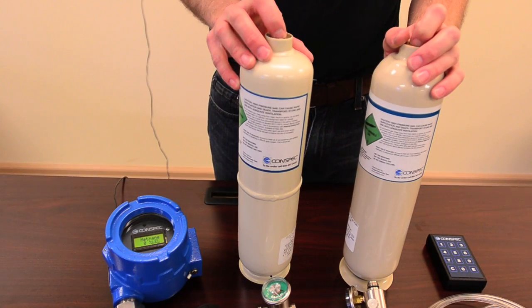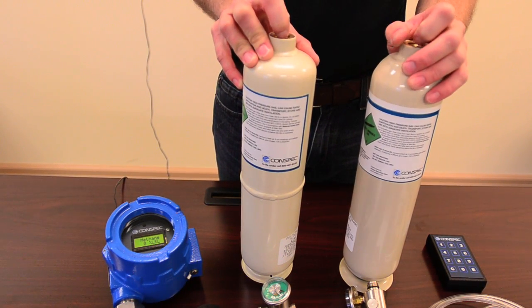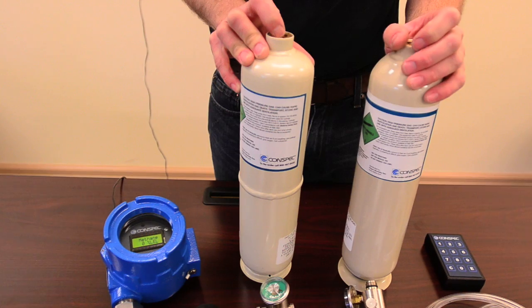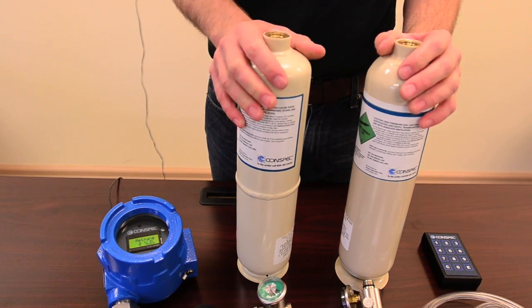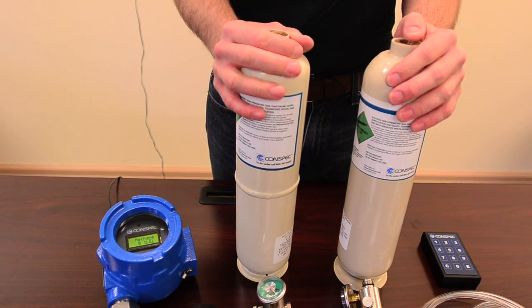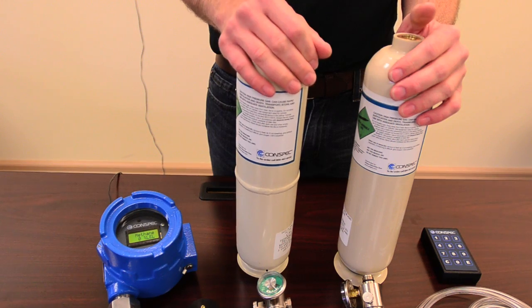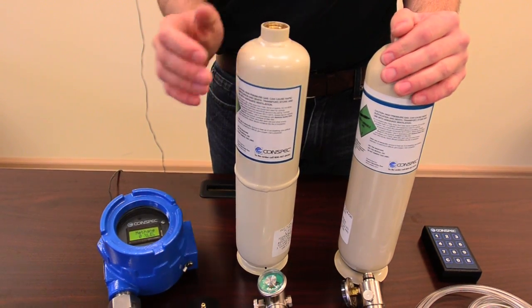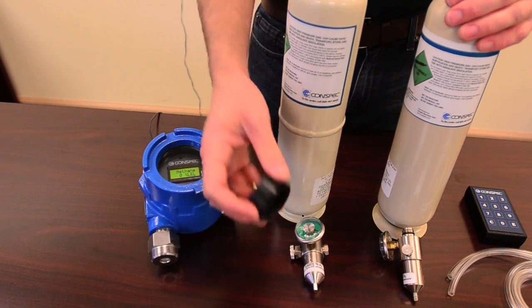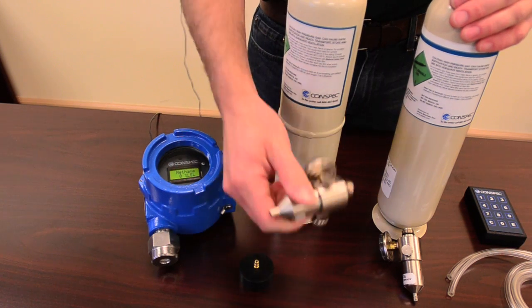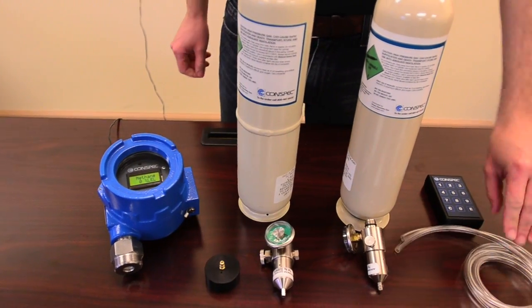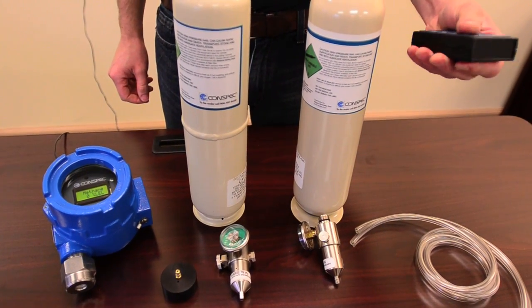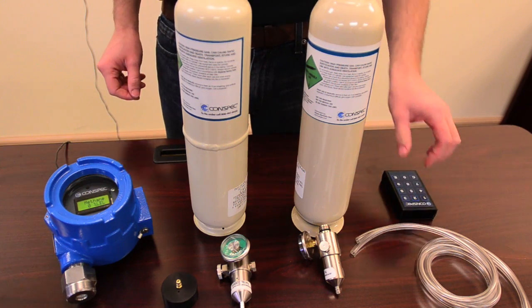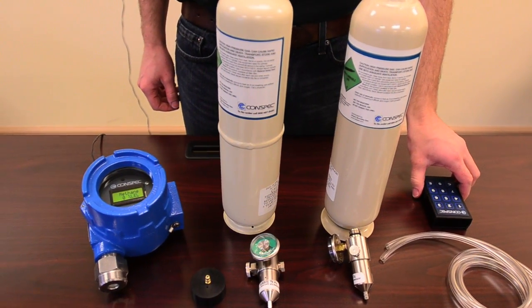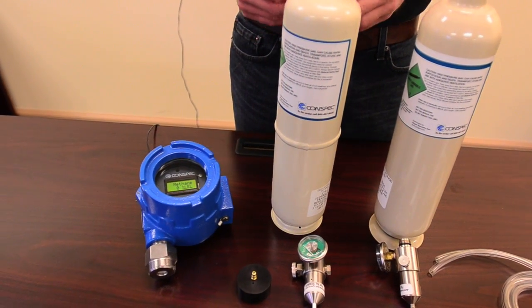You have to perform a calibration on your Conspec Controls Universal Series monitor. You need some basic equipment: first, your calibration cylinders, your span gas and your zero gas, your calibration adapter, your flow regulator, gas tubing, and your infrared handheld programmer. Before you start your calibration, you want to make sure that the monitor is unlocked.